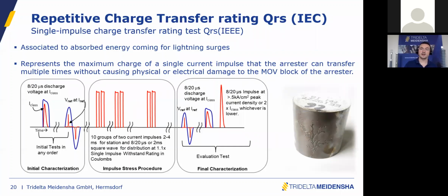Another important energy rating is the QRS test for the charge transfer, also now fully harmonized with IEEE. This has more to do with lightning. The concept of the test is a little different because you are looking at the mechanical integrity of the block. You are doing a kind of statistical analysis because you use many block samples, and this test is only done on the block itself. You are not looking at the thermal behavior. You inject a specific charge, and you want to make sure that this charge does not damage the block mechanically or physically, and that the electrical characteristics measured before are the same after the charge stress.